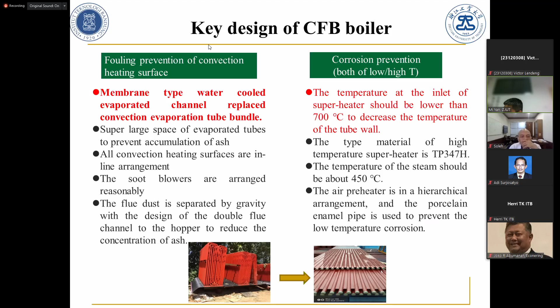And improve the adaptability of the boiler for MSW. So we add a short circuit bypass around the primary air preheater. What does it mean? Usually the primary air after heating will mix with some fresh air, then adjust the temperature. But in case the temperature is lower, we directly use the hot primary air to the furnace. So this is a bypass. And we use more superheated area to ensure the steam temperature, and we use an evaporator channel surface to ensure the production, meaning how many tons of steam should be produced by this boiler.